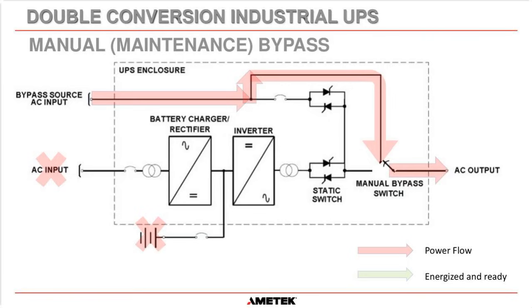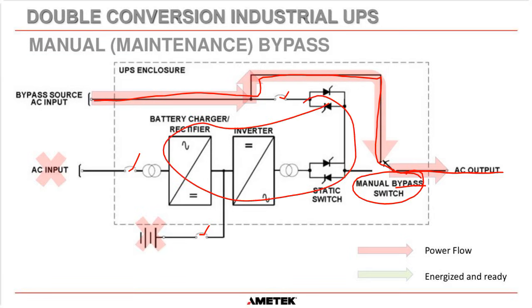And then if you want to do any maintenance on the UPS, you can move the manual bypass switch to the bypass position, and that takes the power around the static switch, down through this bypass switch and out to the loads. You can open this breaker, open this breaker, and open this breaker, and then all these components are de-energized and you can work on them.